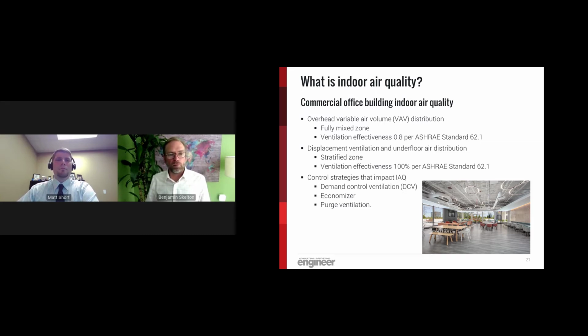One example of that, and probably one of the more typical examples we see in an office building, is the overhead variable air volume distribution system. This type of system, generally speaking, fully mixes the space, meaning all of the air is changed over consistently within the space. It has less ventilation effectiveness, though. As far as getting ventilation to the occupant, we need to factor that in. So when you look into the calculations within ASHRAE 62.1, we have to increase the amount of ventilation distributed to spaces to try to, from a calculated procedure, estimate how much ventilation is actually getting to the occupant zone.